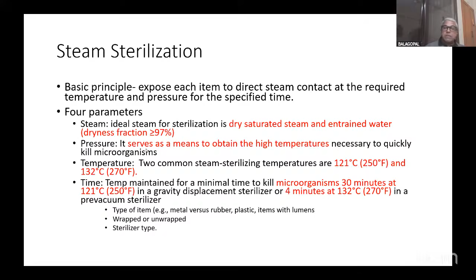These are the 2 temperatures at which it is used. Over a period of time, the 121 degrees centigrade temperature is used for 30 minutes, and the 132 degrees centigrade temperature for 4 minutes. It also depends upon the type of the item, whether it's wrapped or unwrapped, and the type of sterilizer. There are 2 types of sterilizer.